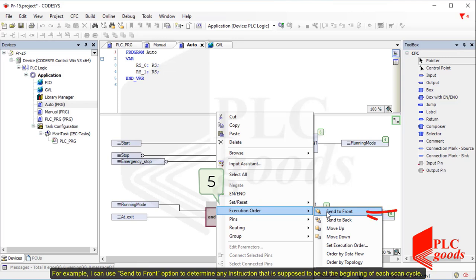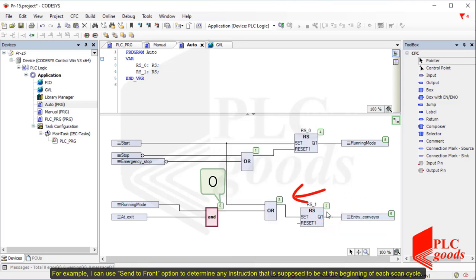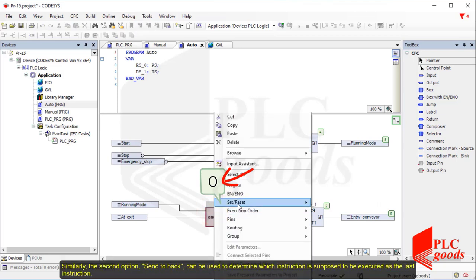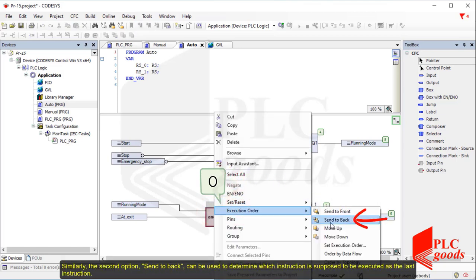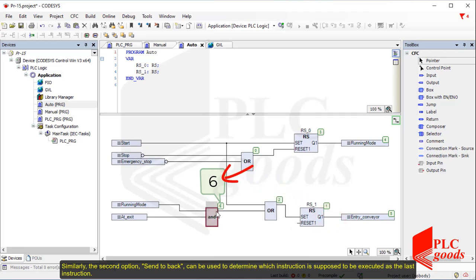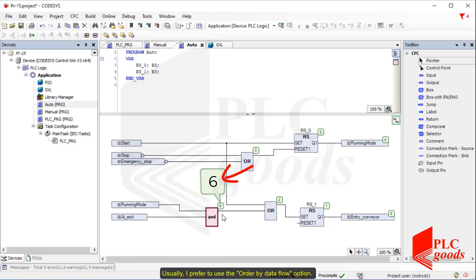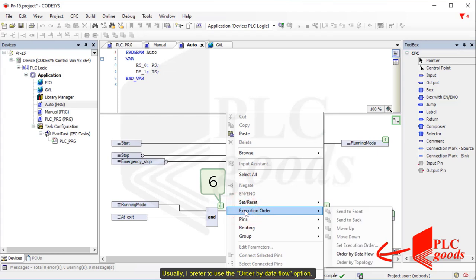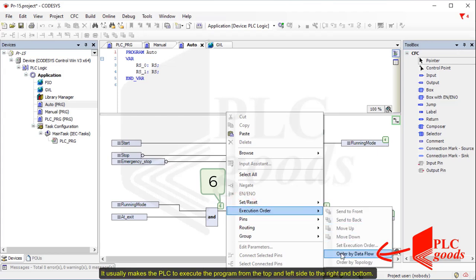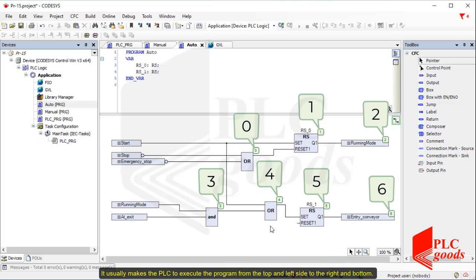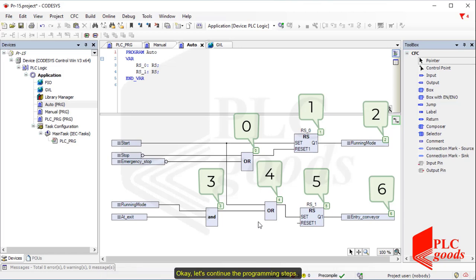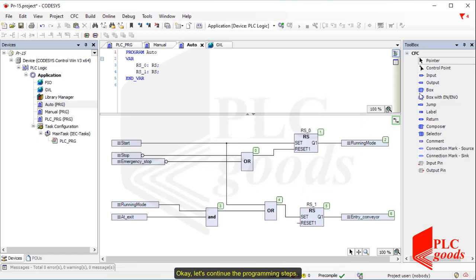For example, I can use the 'send to front' option to determine any instruction that is supposed to be at the beginning of each scan cycle. Similarly, the 'send to back' option can be used to determine which instruction is supposed to be executed last. Usually, I prefer to use the 'order by data flow' option. It usually makes the PLC execute the program from the top and left side to the right and bottom. Let's continue the programming steps.